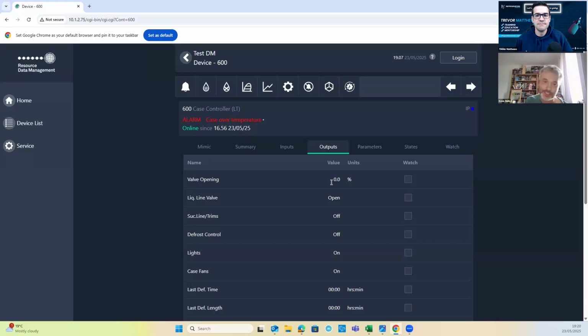Now, I would have loved to have demonstrated that, but unfortunately, all my transducers I've got at home are 5 volts. So you're going to have to trust me on that is what you're going to be checking on your transducer. You're going to need to put some parameters in your transducer to get it to read anyway, which we'll come to in a minute. But bear in mind, on a 4 to 20 milliamp, if it's open line, you'll get a fault because it needs 4 milliamps to say 0. Yeah.